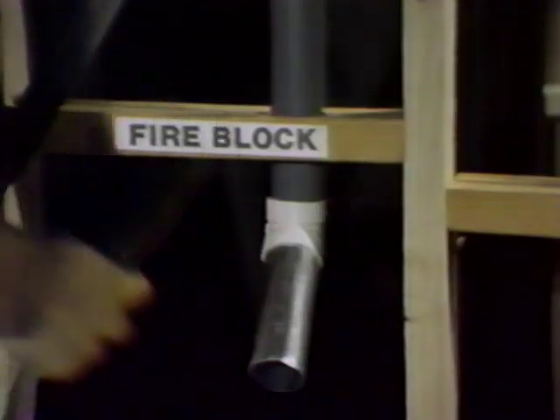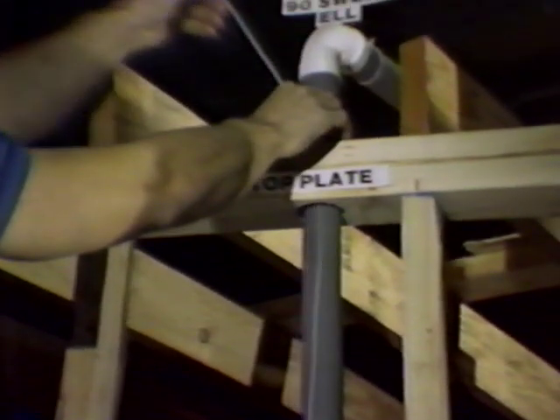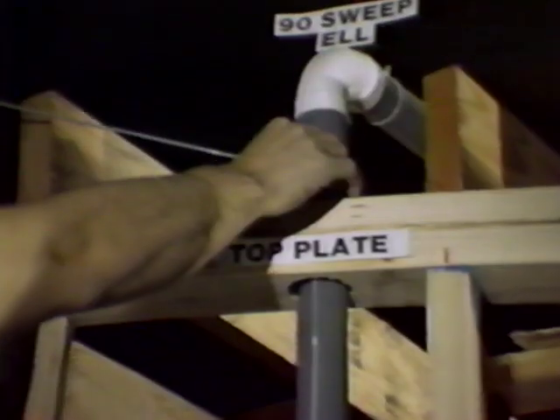Next, you will need to install the 2-conductor low voltage wire. Like the vacuum lines, you can run one main low voltage line and branch off to each vacuum inlet. The wire should be run through the same holes as the vacuum tubing. Run about 12 inches of low voltage wire through the bottom hole in the mounting plate. Secure the wire to the vacuum tubing with plastic wire ties or electrical tape. Insert the loose end of the wire through the front opening of the mounting plate, and to assure that the correct size hole for the vacuum inlet is left in the drywall, you will need to install a plaster guard.